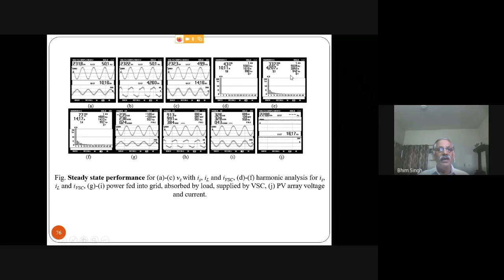So it works very well even in the nonlinear load condition. We are able to push power at almost unity power factor with very low THD around 4.3%, where the load THD is quite high, around 33.7%.